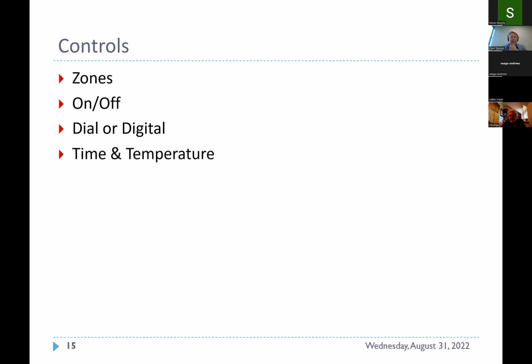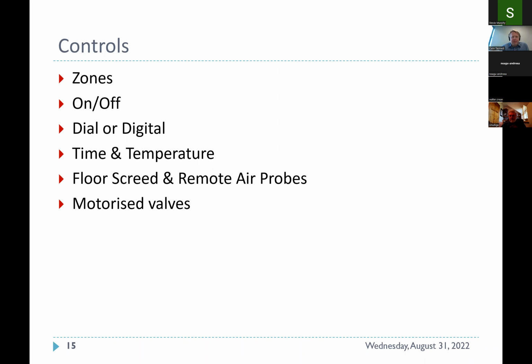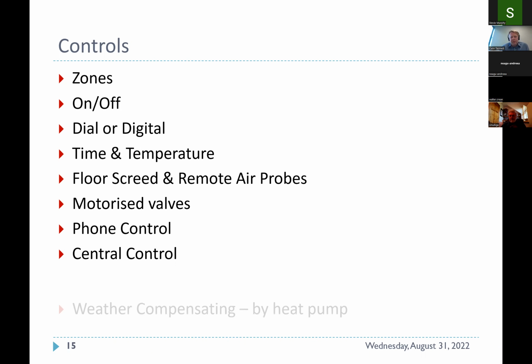We can use thermostats, either set point, dial, or digital. We use programmable room thermostats to give us time and temperature control, depending on the application. We can have air probes or floor screed probes. Like if you have a 230-volt system throughout the house, you'll not be allowed to put that into a bathroom. Therefore, if you have floor heating, you can put a screed sensor, or you can put an air probe. Motorized valves are typically used, and then you look at more advanced controls via apps or centralized controls.